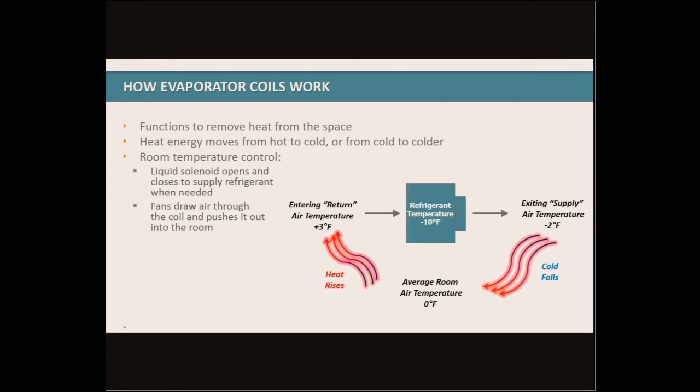To start out, I want to go back to the basics on how evaporator coils actually work. Evaporators function to remove heat from the space. In particular, heat moves from hot to cold, or in the case of evaporators in refrigerated spaces, it moves from cold to colder locations. The evaporators are controlled through either temperature sensors or through thermostats. The basic operation is that they open and close the refrigeration solenoid valve to allow refrigeration to enter the evaporator coil when refrigeration is needed.